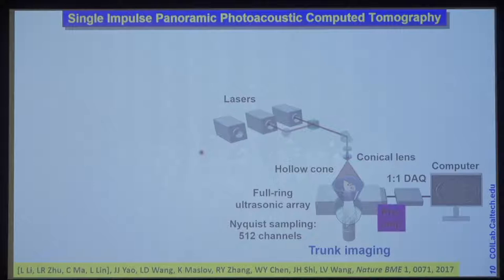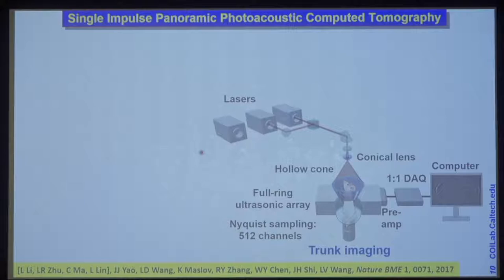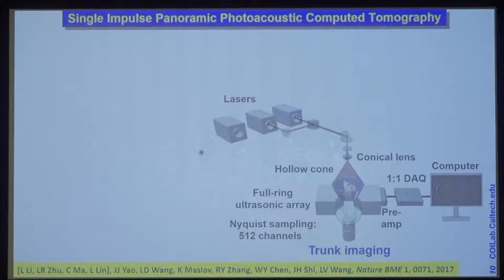To image deep into tissue, because the signal becomes weaker exponentially toward the middle of the animal, you want to preamplify the signal before cable noise creeps in. We have a one-to-one mapping for data acquisition, so a single laser shot gives you an image. All data is acquired within the acoustic transit time, which translates to about tens of microseconds — that's how fast we can get an image, so you don't have to worry about any motion artifact.